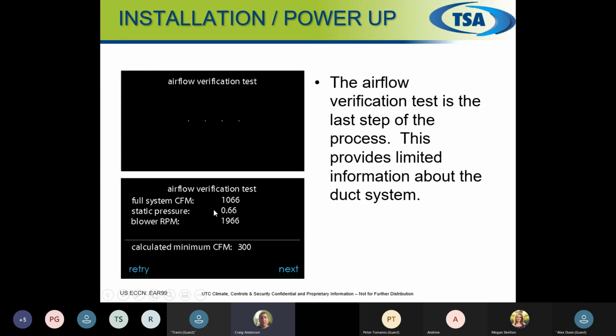So once this comes up, you could look at it, hey, there's our static pressure 0.66. This is fantastic. We have a great system. The furnace is going to be able to operate at this. If you see that static pressure out of the range, if we're into the 1.2s or we're real low, then, hey, we need to look at something. So great stat for that. It gives us the opportunity to measure this without using your external tools. The furnace is doing it with the motor.